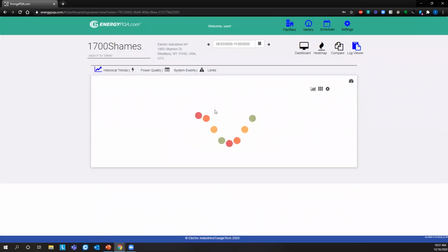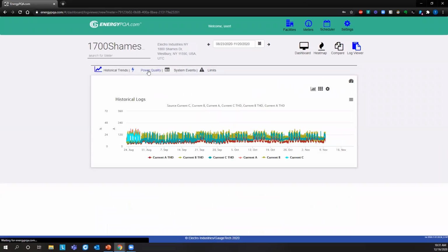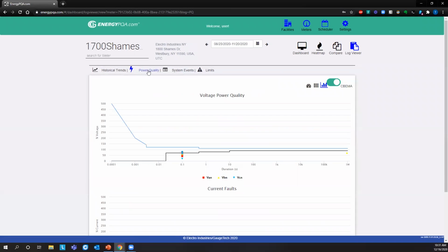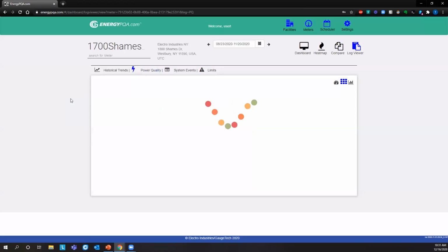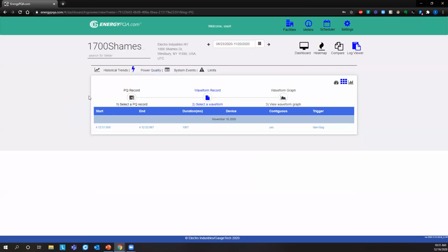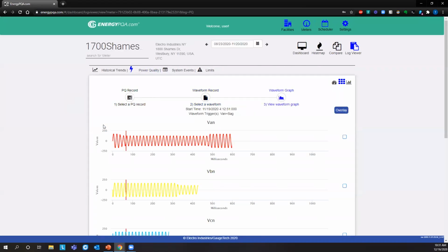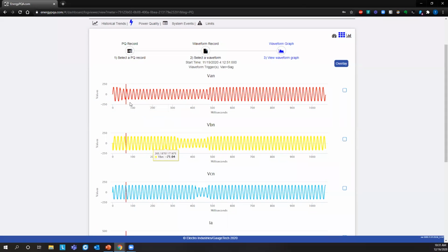With our log viewer software, we can view any of the historical trends from the first page. We can also look at the power quality. And now when I click on this item, there's a sag event. I have waveforms for this event. So when I click here, I can come in and look at the waveforms. So now I saw that this sag lasted several cycles.